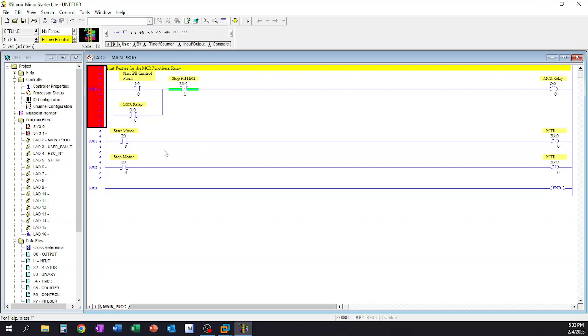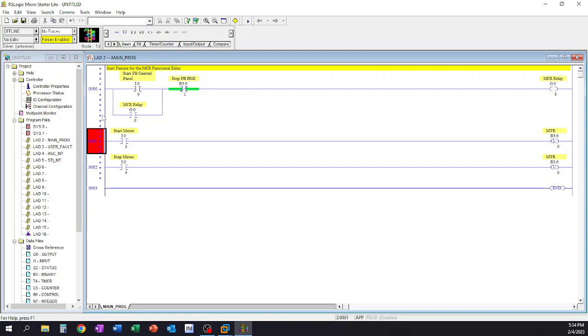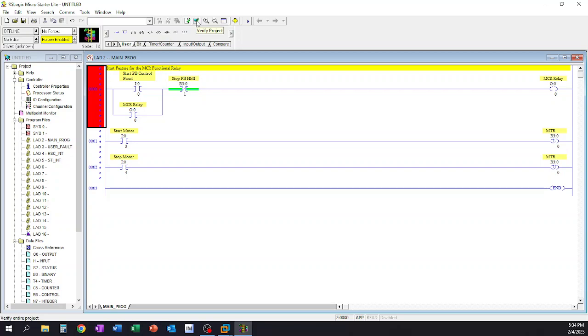That's going to verify this ladder. It's only going to verify and check that this ladder is correct and up to date. This other one over here is the verify project and it's going to go through all of our ladders and routines and make sure that they are up to par, the syntax is good, everything is standard and good. Depending on what you're wanting to do, depending on how big your project is, if your project's huge it's going to take a while for the verify project to go through. If you're only wanting to work with one routine at a time and you only want to check that, you can verify the routine as well.